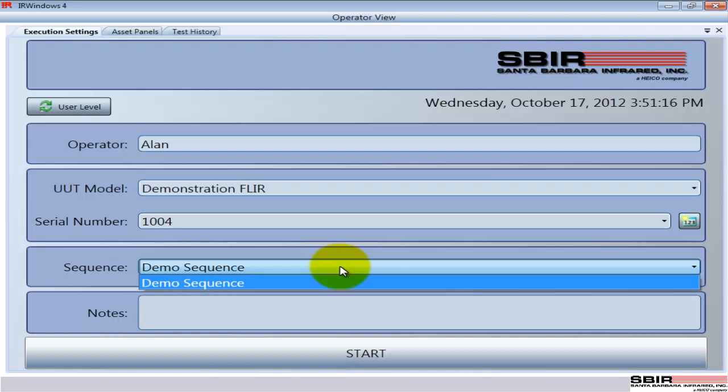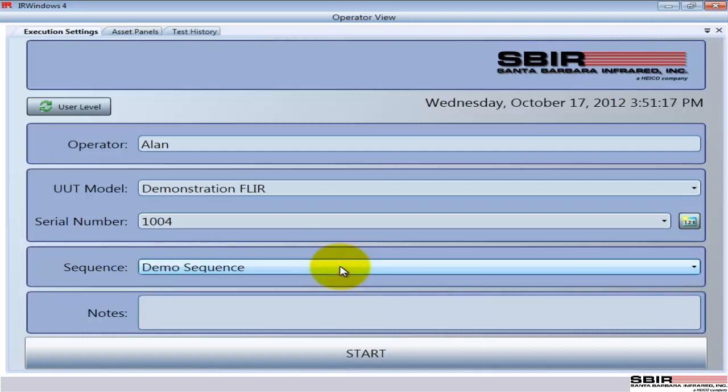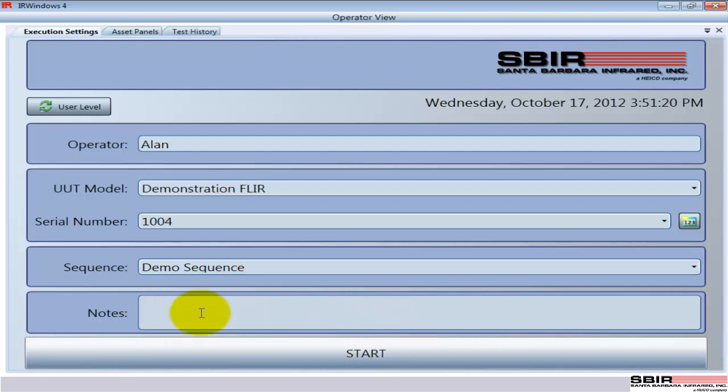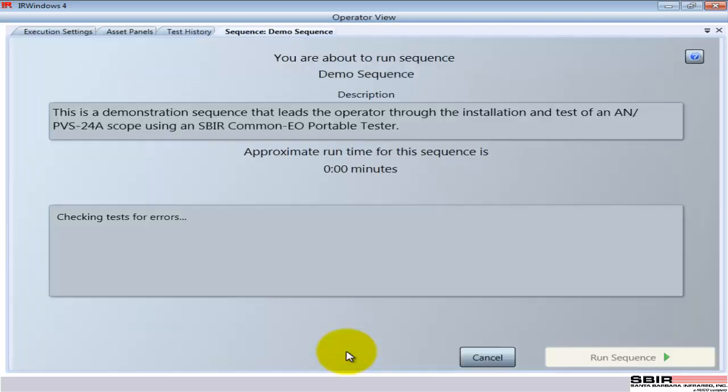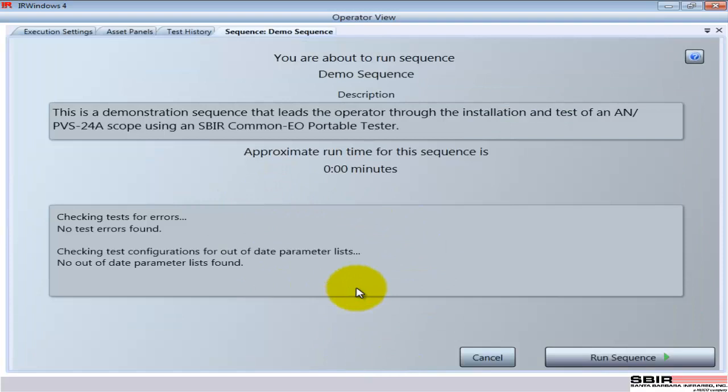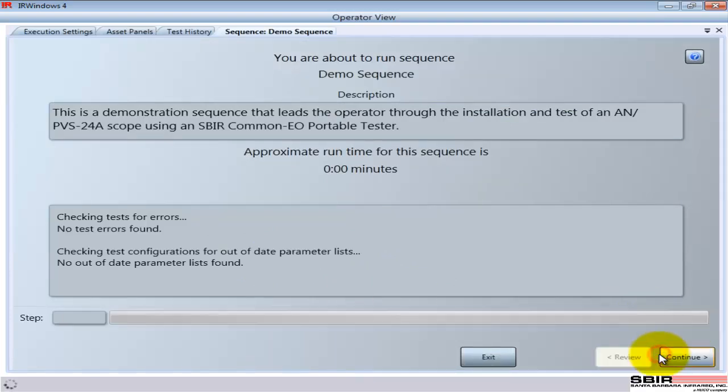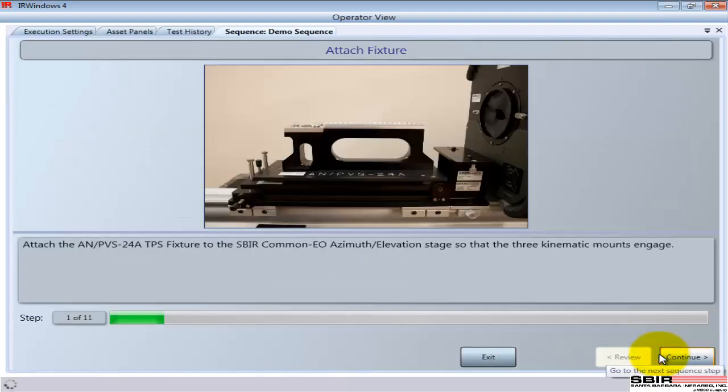If it's a production environment, it may be a single sequence, but we're just going to run this in this case. There's also a place for notes if your particular lab wants to record things like environmental conditions or whatever is important to you to record around a sequence. So we'll get it started, and the first thing that happens is it does a quick check on the sequence to see if there are any problems. There are no errors, so we'll start its operation.